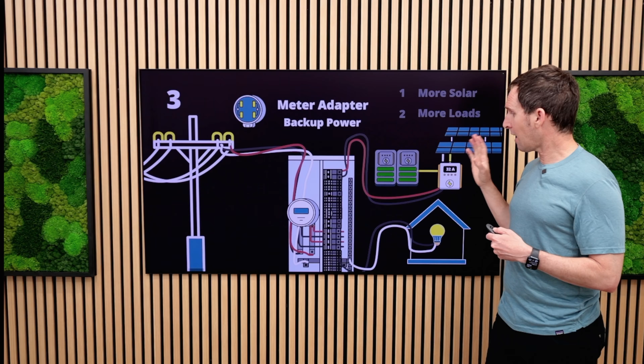Okay, so the anti-islanding rule says that the inverter needs to see a source of voltage and a frequency from the grid, and the way they provide that for backup is actually from a battery system. Typically the battery will simulate this, it'll create this voltage, create this frequency, and that tells the inverter it can turn on safely. But even with the battery, we need a point of separation so that if this system is operating, there's no safety risk to the grid itself.